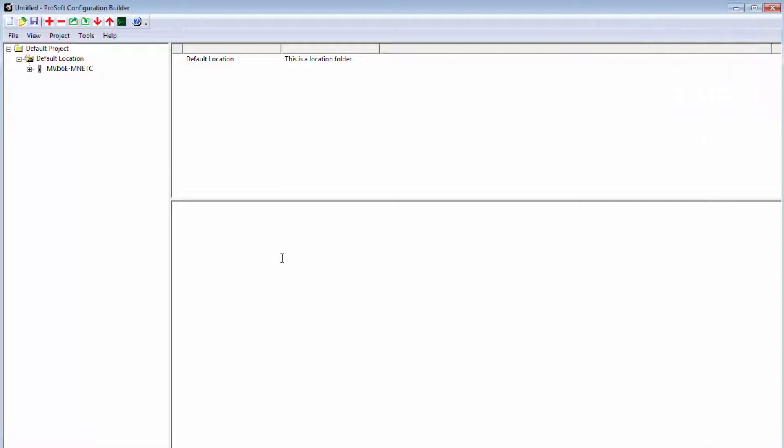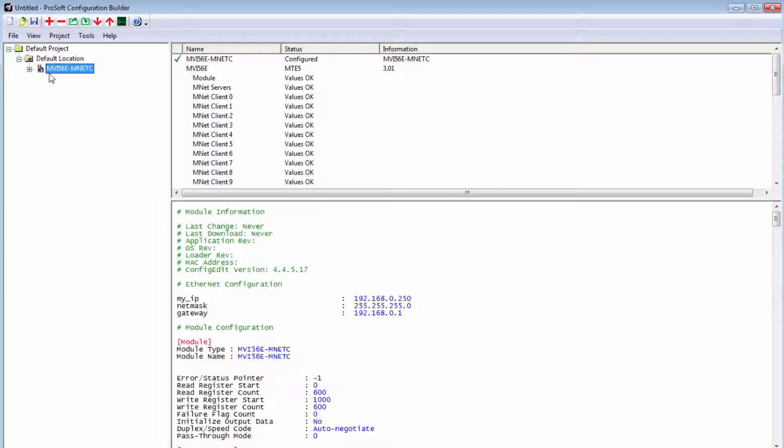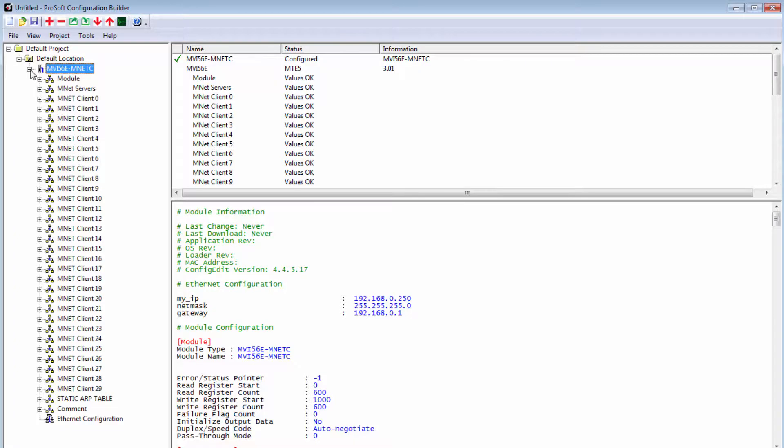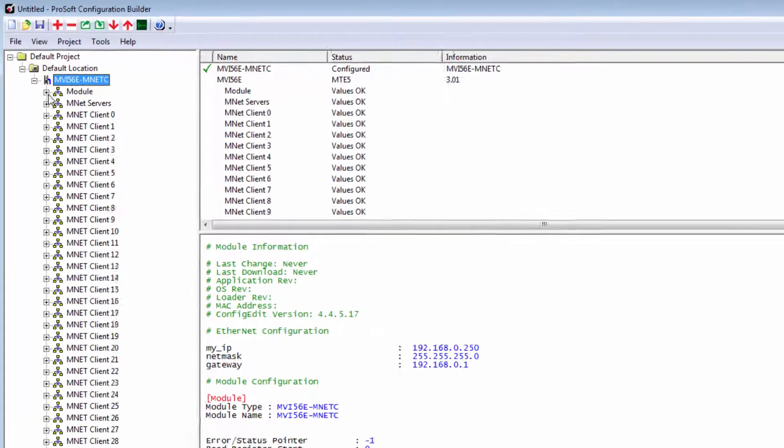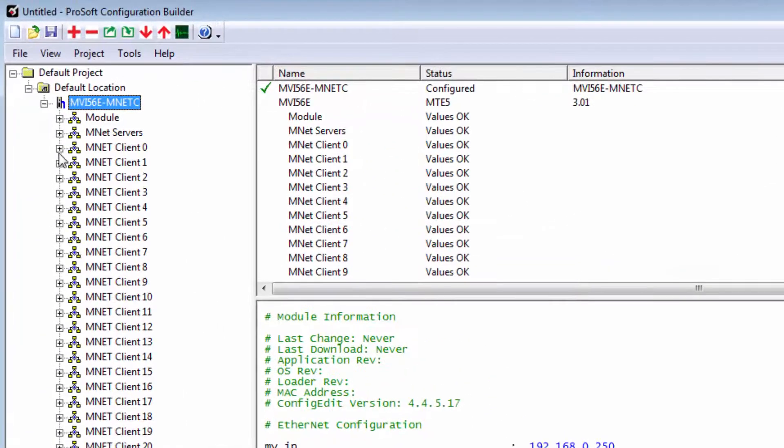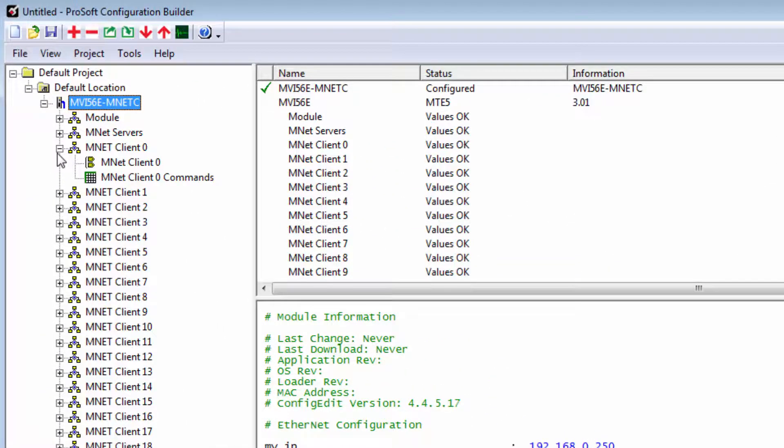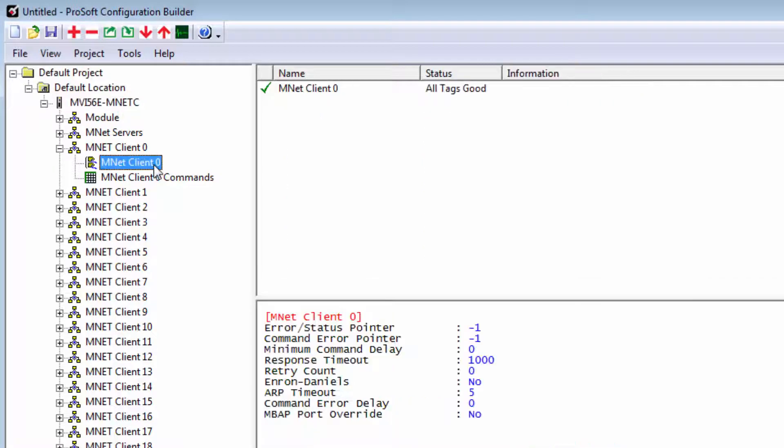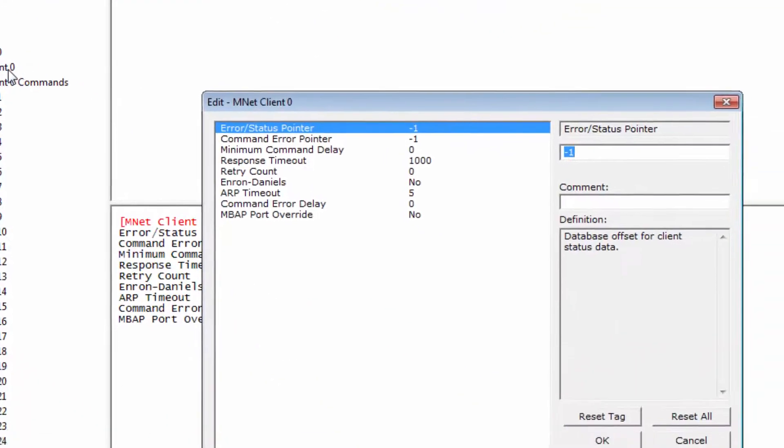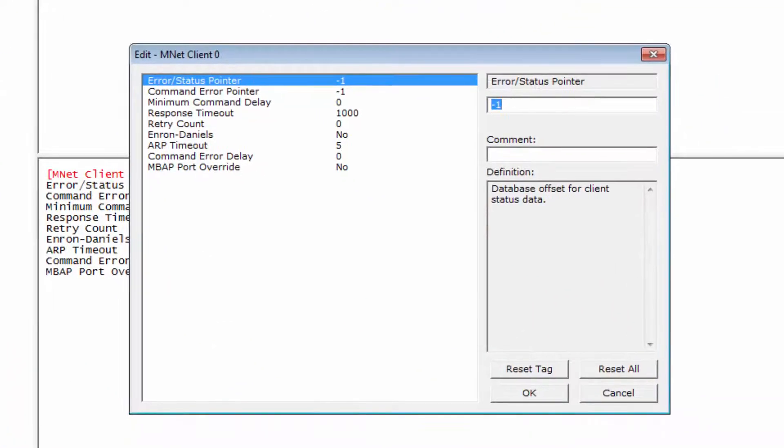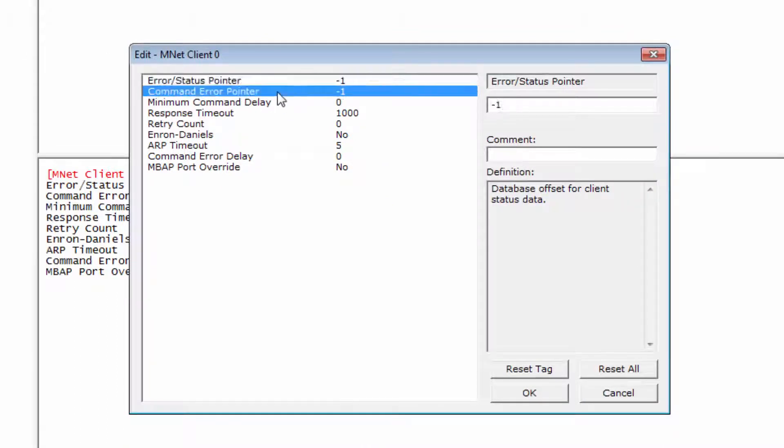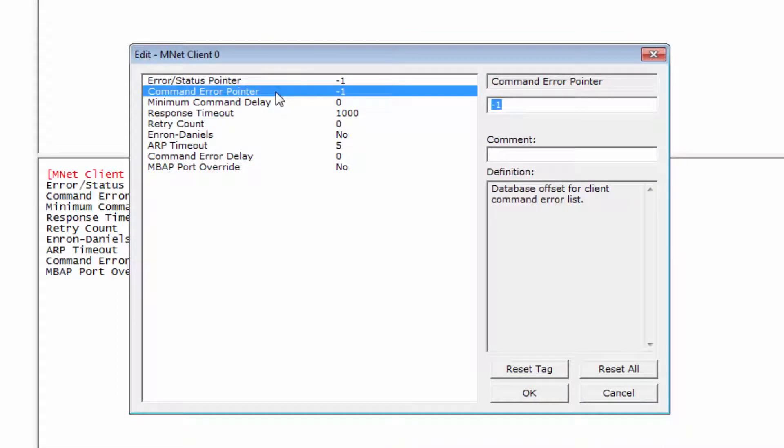In ProSoft Configuration Builder, or PCB, once I have my module selected, in this case an MVI56E MNET-C, I'll click the plus sign to expand the module configuration parameters and then expand MNET Client 0 information. Double-click on the Client 0 icon to open an edit window and here we can change the module database options. Second from the top, we have the Command Error Pointer.